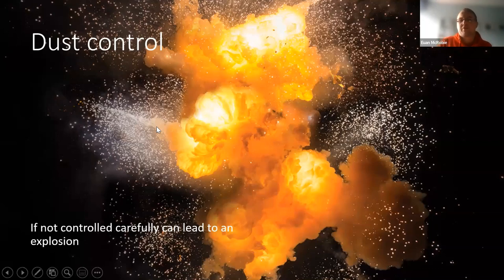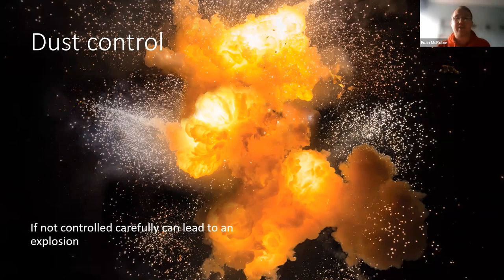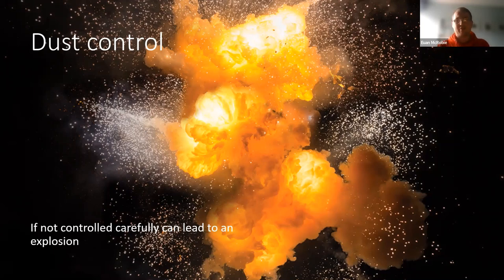Dust control: dust isn't just a health risk — it is also explosive. When packed to a sufficient concentration and reaching auto-ignition temperature, it can create an explosion force. There was a case study where a dust explosion killed many people because the filtration system wasn't being cleaned. Ensure regular dust control measures are in place: any cutting equipment should have a dedicated extraction source, and correct HVAC systems should be in place to mitigate dust on site.